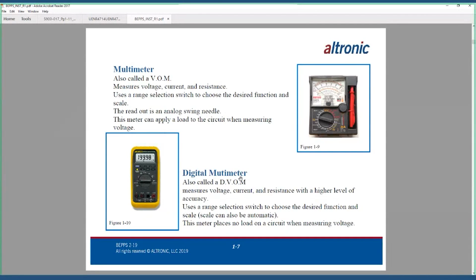There's multiple brands out there. You don't have to go out and buy a Fluke if you don't have one. But that said, I would also steer you clear of going to the Dollar General store or Harbor Freight Tools and buying the $5 digital volt ohm meter and trying to use it. If you have a faulty meter or an unreliable meter, you should just throw it away and go get a good one, because if you're getting false readings on the system that you're trying to troubleshoot, it's going to catastrophically cause you to go down the wrong rabbit hole.